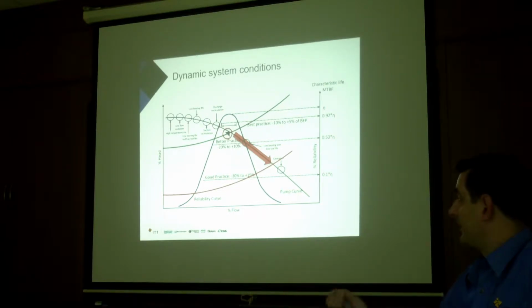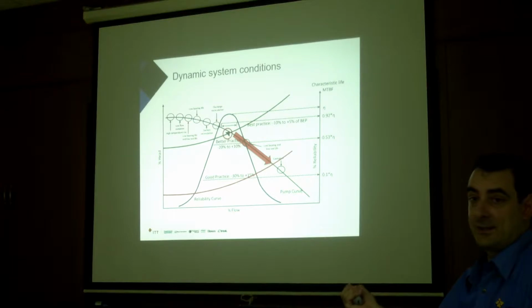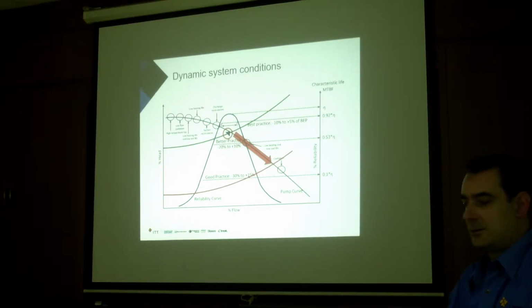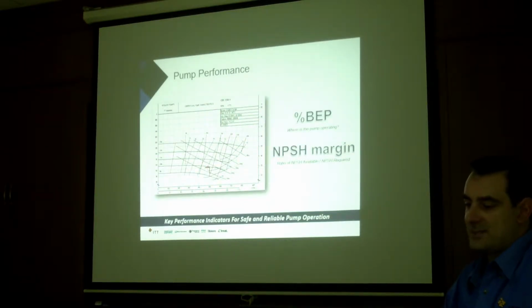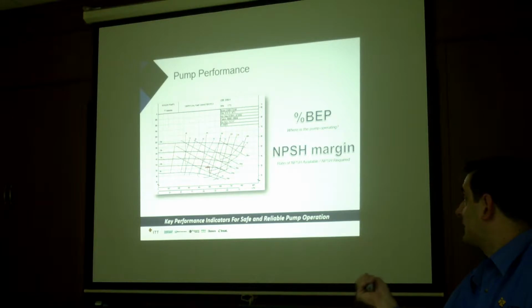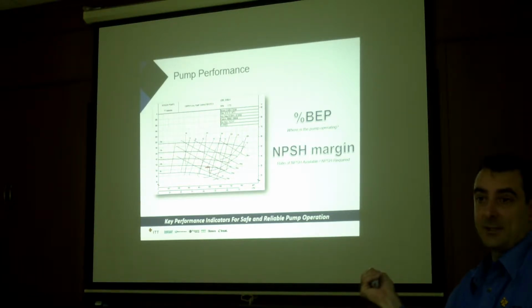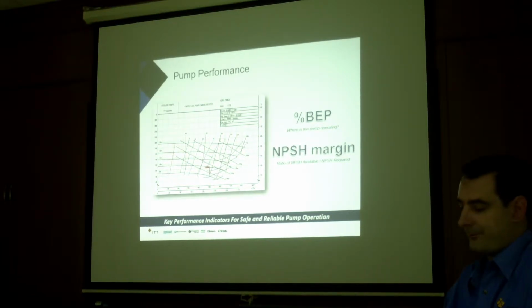I have lots of applications where the customer runs here all the time. It's not good, but the pumps sometimes survive. But if they start running here off the end of the curve, usually that's when we get shaft failures and things like that. High maintenance costs. So again, it's understanding where we are. So these are the two things that we really look at compared to a variable speed drive, the normal one.